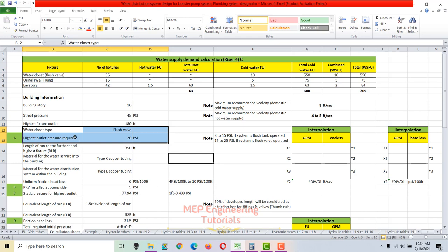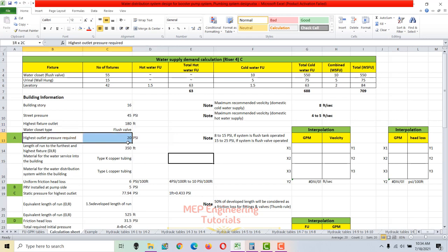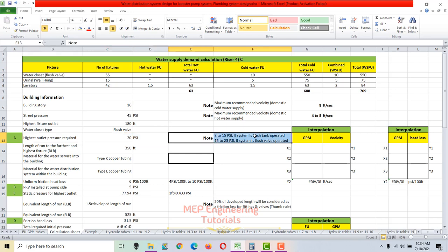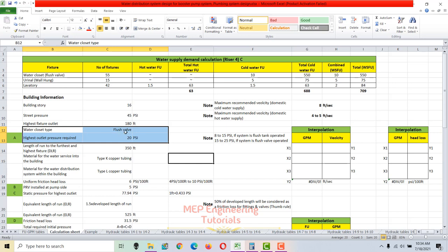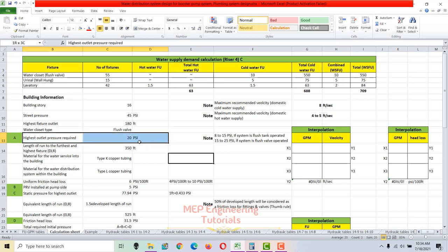The highest outlet used is a water closet, and it is a flush valve operated water closet. Based on the notes: if the system is flush tank operated, use 8 to 15 psi; if flush valve operated, use 15 to 25 psi. Since our case is flush valve operated, we use 20 psi as the highest outlet pressure requirement.